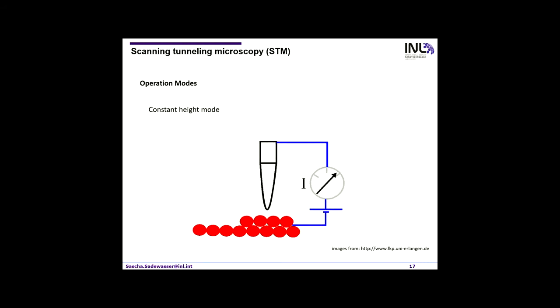And there's another way to do this, which is to use constant height mode. So here you're actually keeping the tip always at the same height, and then you're measuring the current. So if you're on the lower step, you have a lower current. On the higher step, you have a higher current. This is much faster because you don't need to do the feedback, so you don't have a controller to do the feedback. But you only get relative information. So you cannot really know how high your step actually is.